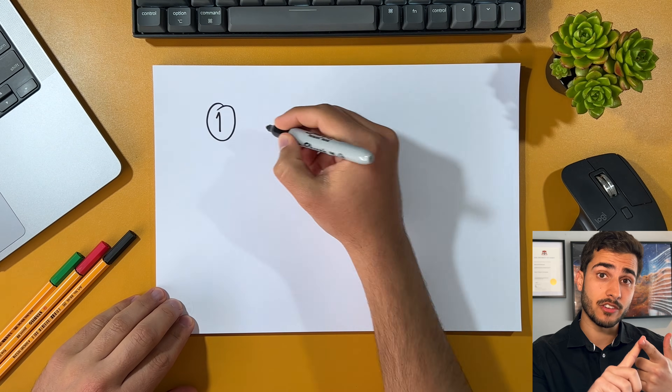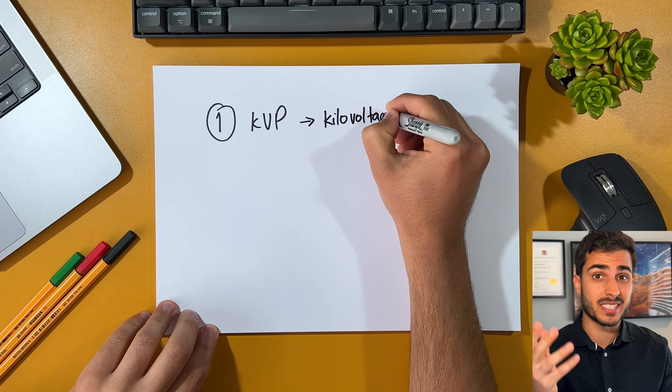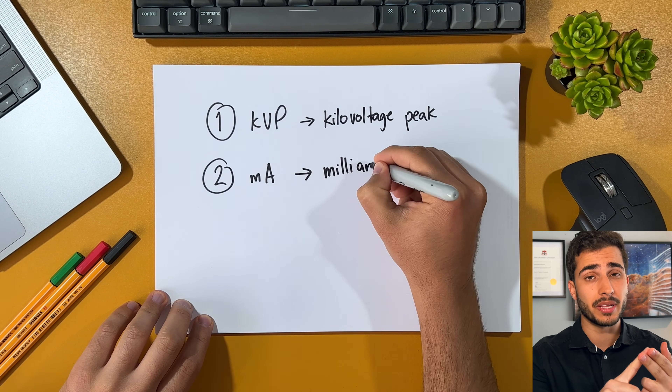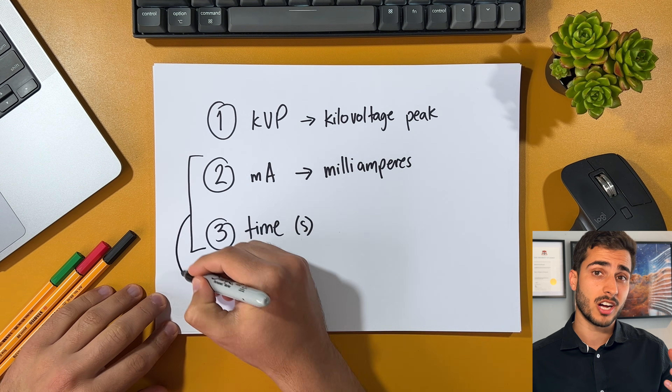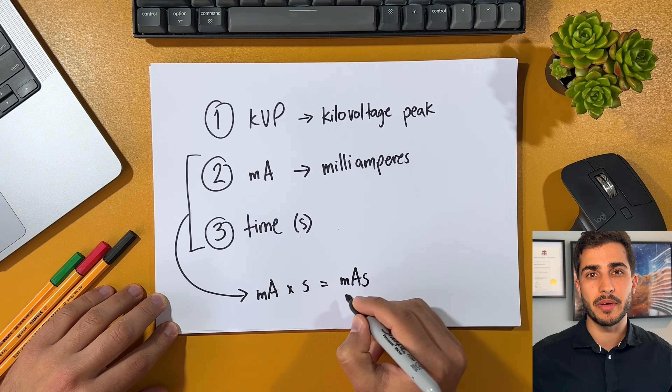We can adjust the x-ray beam of an exposure with three key primary factors: the KVP, or the kilovoltage peak, sometimes referred to as KV for convenience; MA, the tube current in milliamps; and time in seconds. Often the current and time are combined or multiplied together to give the MAS. I'm going to take you through each of these factors so hopefully we can understand what they're all about.